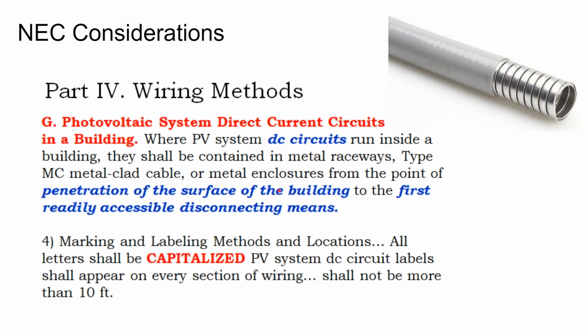Where DC circuits run into a building, they shall be contained in metal raceways and have a disconnect at the first readily accessible means. Well, this is a solar requirement, but how it applies to batteries is, if you go through a wall with your battery bank, you need a disconnect switch on both sides of the wall.